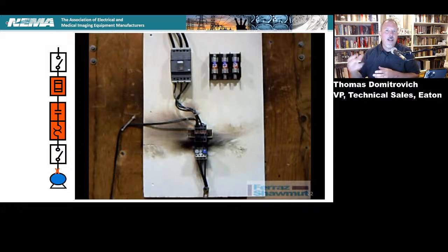There are certain tests that it has to pass after you do the test, and it's not as popular to be specified that way these days. But it really does a lot for the electrical worker, because if you think about it, if there's a problem in that equipment, you can be in front of it. It may not burn you, and it may not create a big arc flash blast, but it can create an unintended rapid disassembly in the field that would not be very attractive. But a type 2 type of application, you would not have that level of damage at all.